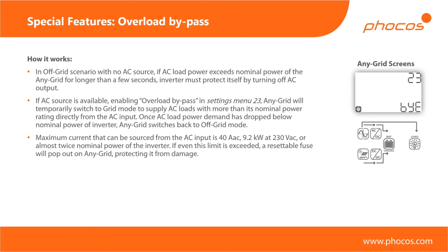So you might ask yourself, what happens if I exceed even that? Well, at some point, because the power is flowing through the inverter, it has to protect itself. At some point, the traces and the cables would overheat. So we have an integrated resettable fuse, which I showed you at the beginning of the session, which will simply pop out if that risk happens. And then it's up to you to just put it back in. There's no need to buy any fuses or anything, but that's just the ultimate layer of protection for the AnyGrid to protect itself.